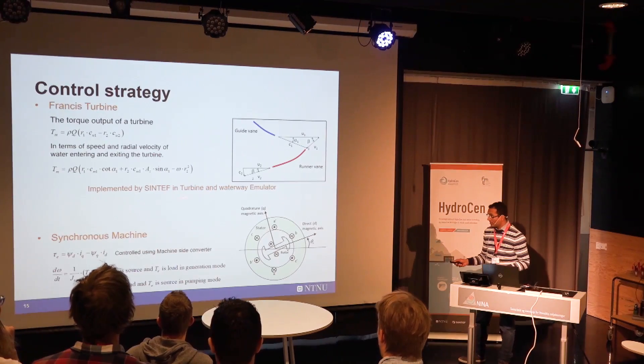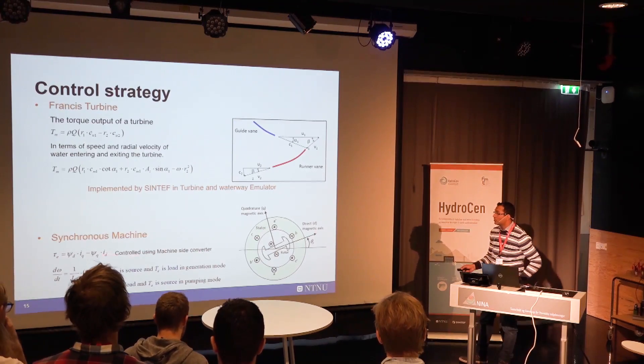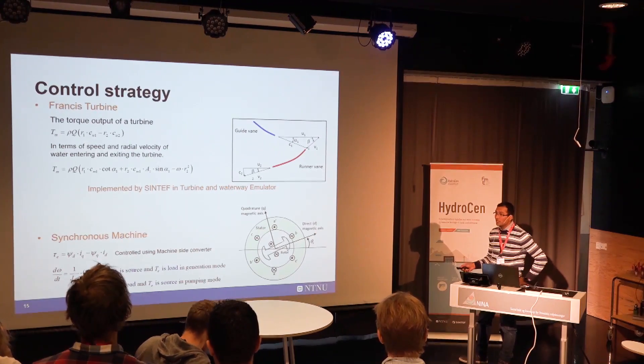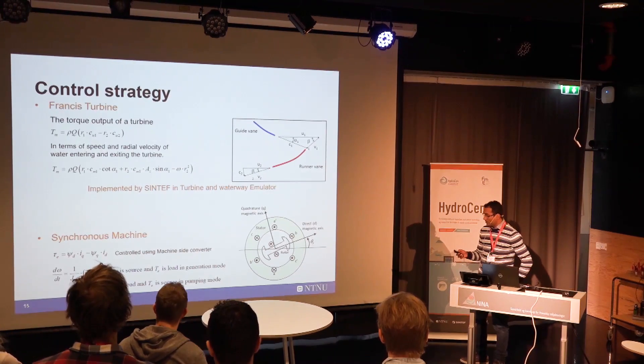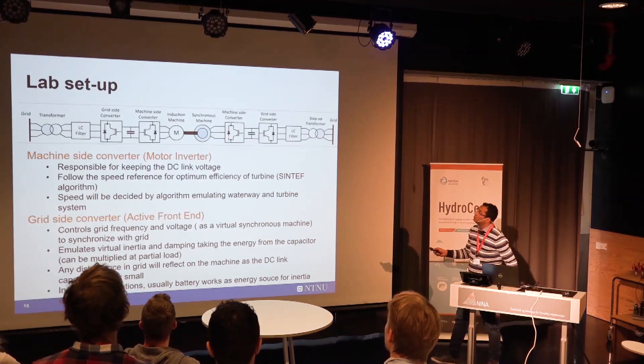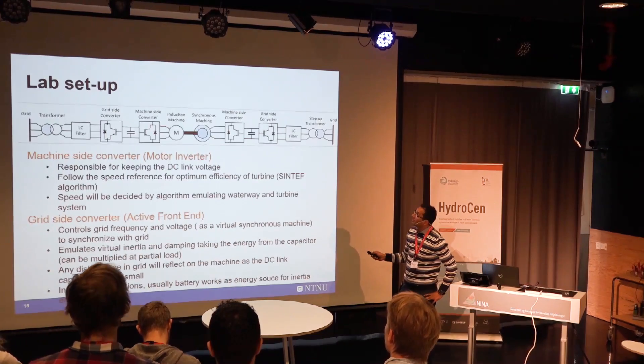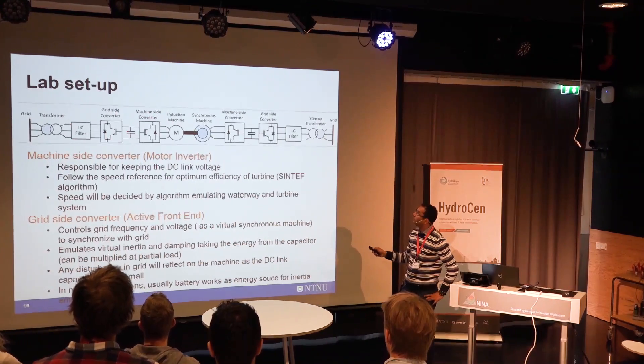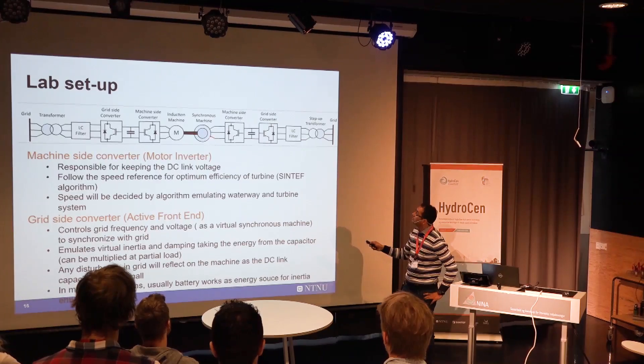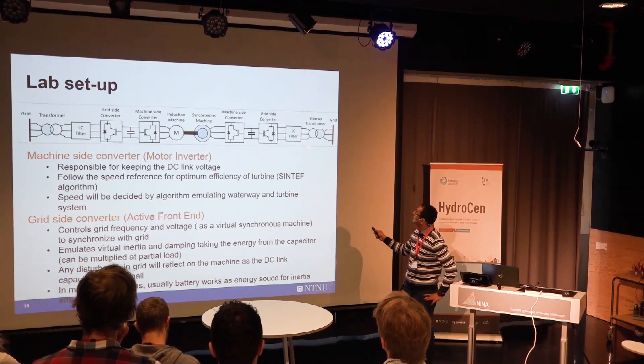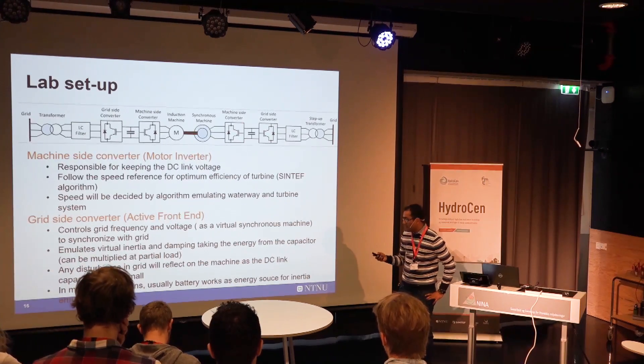In my current work I am using a two-level converter, and if time permits we will work with MMC as well to see if we can meet the challenges. The control strategy involves the torque coming from the Francis turbine — we control the torque from the synchronous machine using the converter to govern speed to the desired level. In my lab there will be two sets of converters: one emulating the turbine side and one for the machine side, with the synchronous machine connected to the grid. I will do experiments with the converter inserted between the machine and the grid.